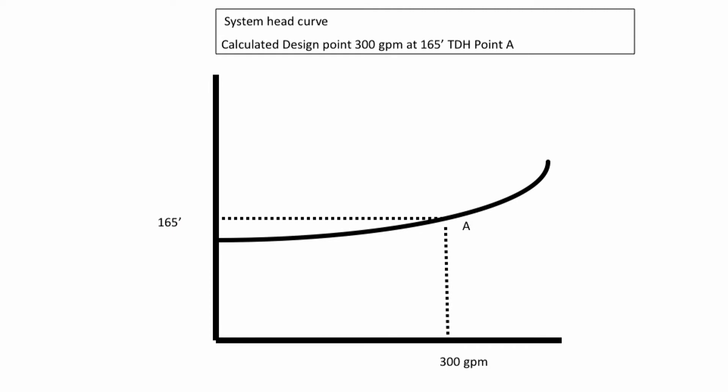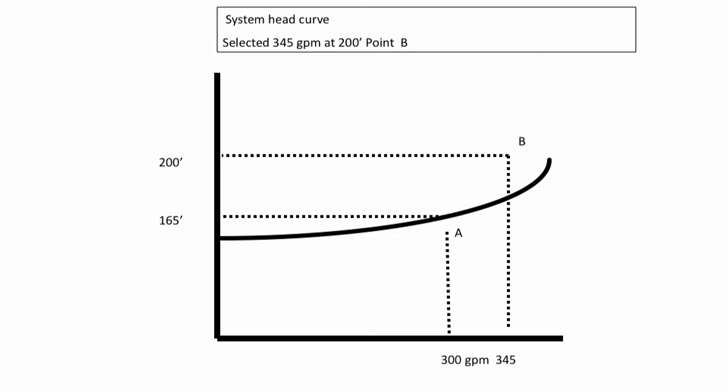The static head and the friction head are plotted. This is what you predict. And your design point is 300 GPM at 165 feet. This is point A. Let's say you add a safety factor of 15% on flow and 20% on head, which means you specify a pump for 345 GPM and 200 feet of head, point B.